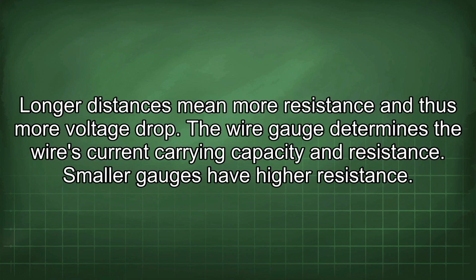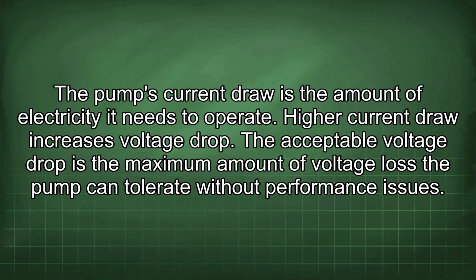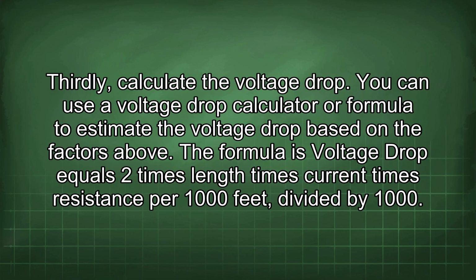The wire gauge determines the wire's current carrying capacity and resistance. Smaller gauges have higher resistance. The pump's current draw is the amount of electricity it needs to operate. Higher current draw increases voltage drop. The acceptable voltage drop is the maximum amount of voltage loss the pump can tolerate without performance issues. Thirdly, calculate the voltage drop.